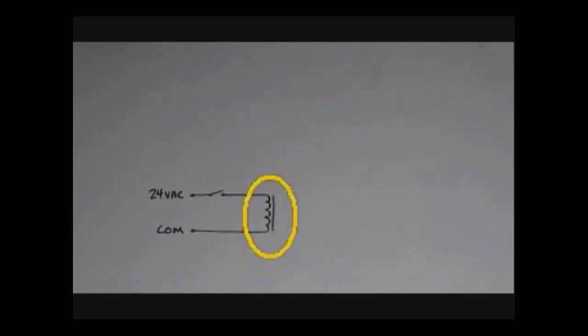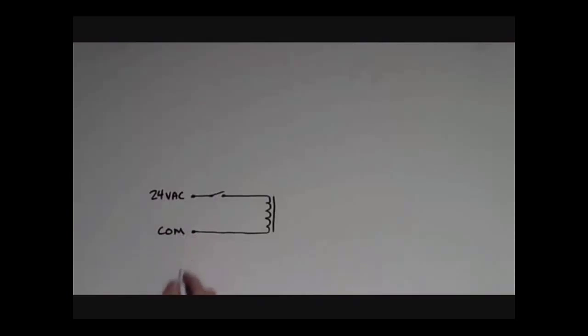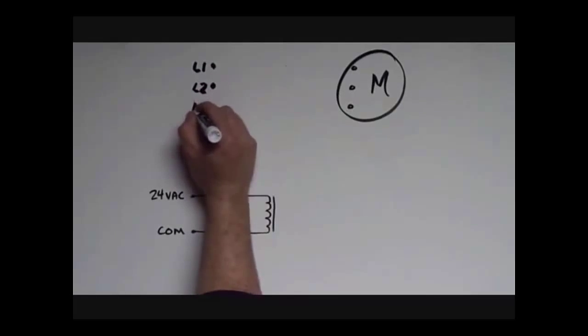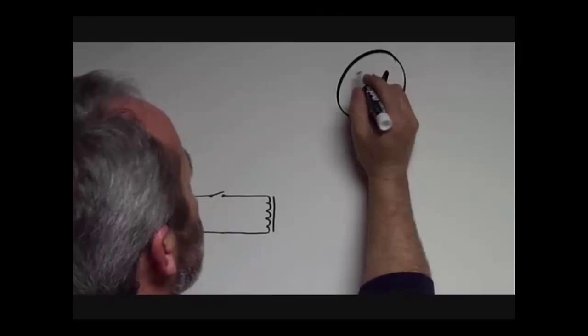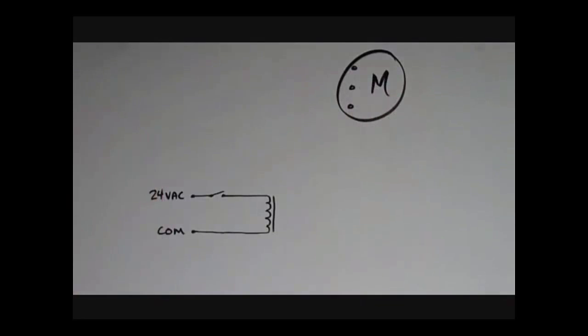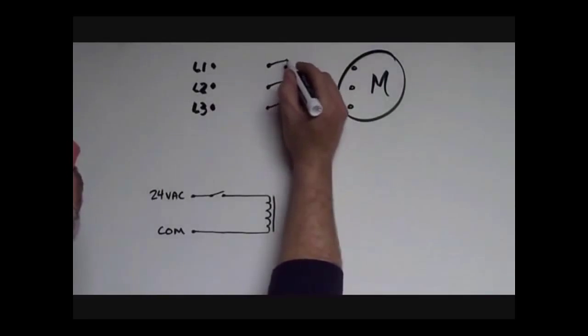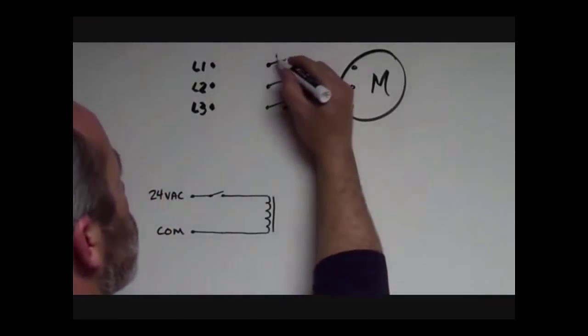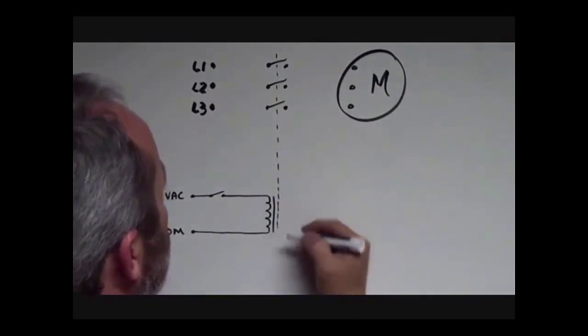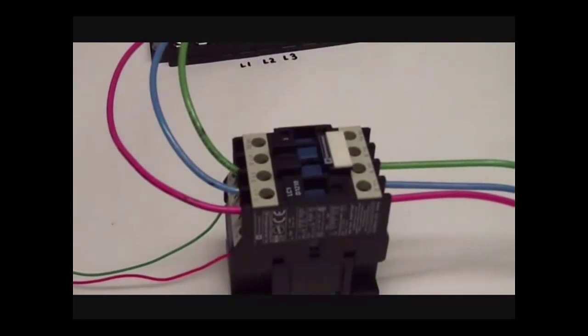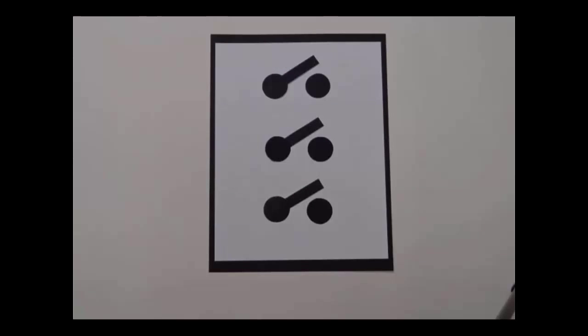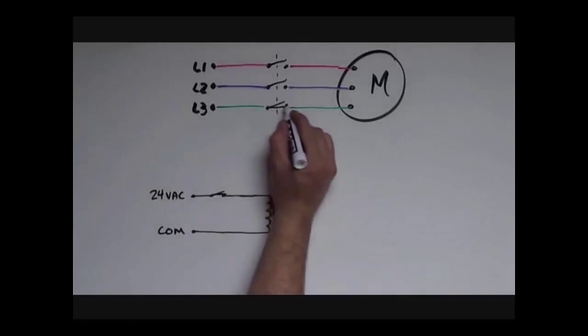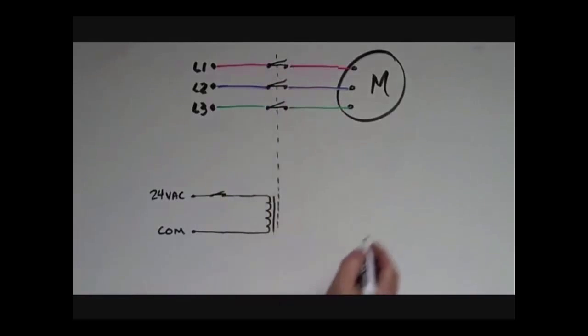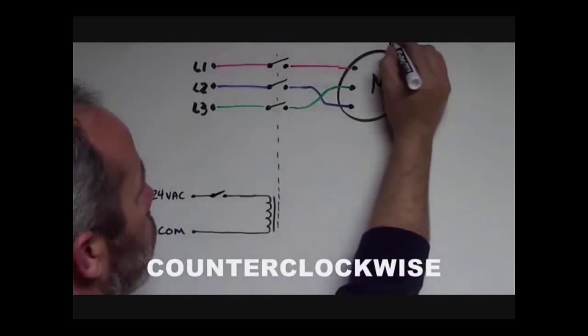We have the 24 volt coil with terminals A1 and A2. We have our 24 volt power supply and a switch to make or break the power to the coil. This is our constant 460 volts from the building power in 3 phases. This is the motor with its 3 terminals, and these are the 3 poles of the contactor that will open and close together when the coil is energized. This dashed line represents the magnetic force from the coil that pulls the contacts closed. So when I energize the coil by pressing the push button, it closes the main contacts and connects lines 1, 2, and 3 to the motor's 3 windings labeled 1, 2, and 3 respectively. If I were to swap any 2 of the 3 phases, the motor would run in the other direction.